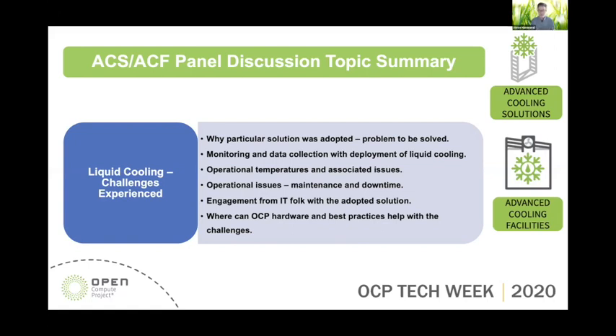If you're pulling air in, your vacuum pump is going to be working harder, and that comes back to what you're monitoring. So you want to monitor the vacuum pump activity. Also, we insisted that our racks have leak detection rope, if you will, inside. So if any water was detected, that was through a connection all the way back to the panel.